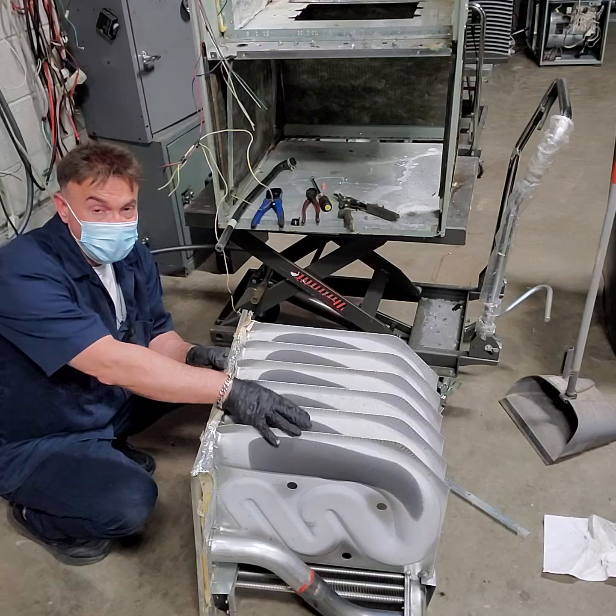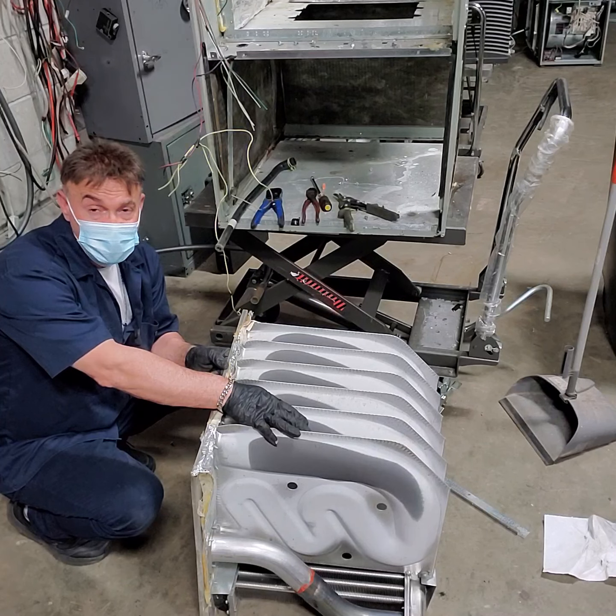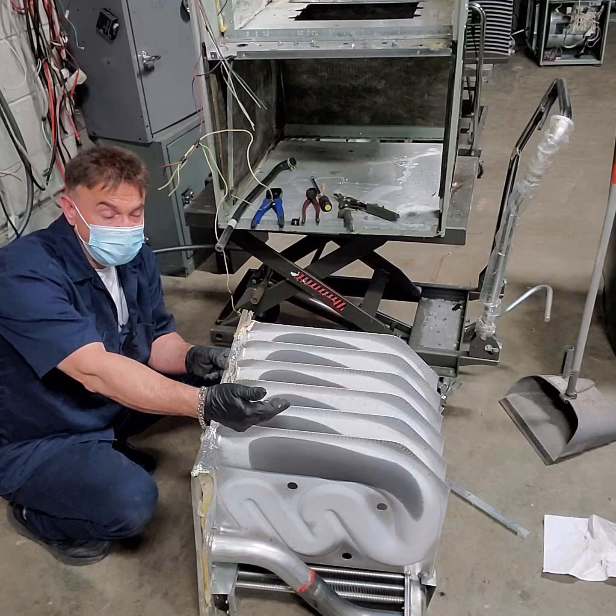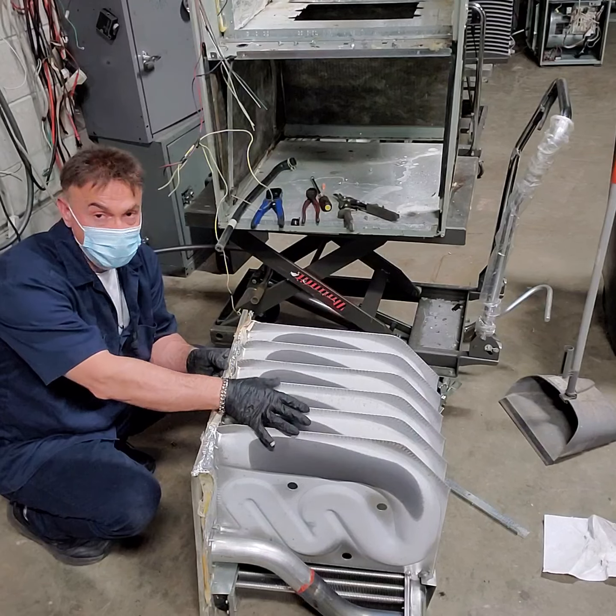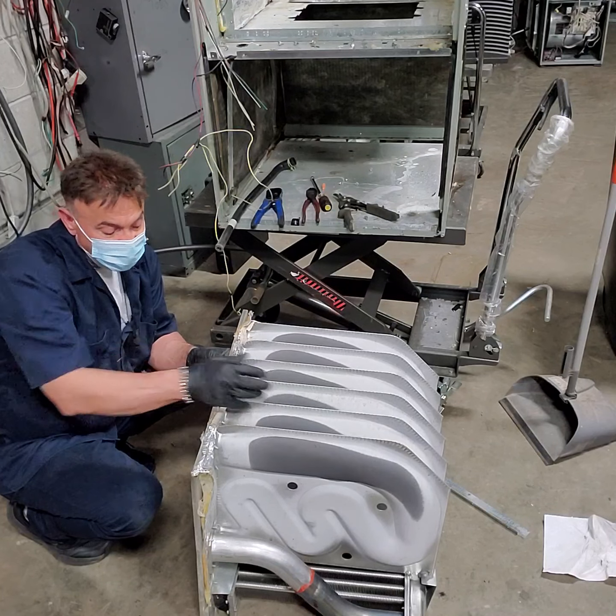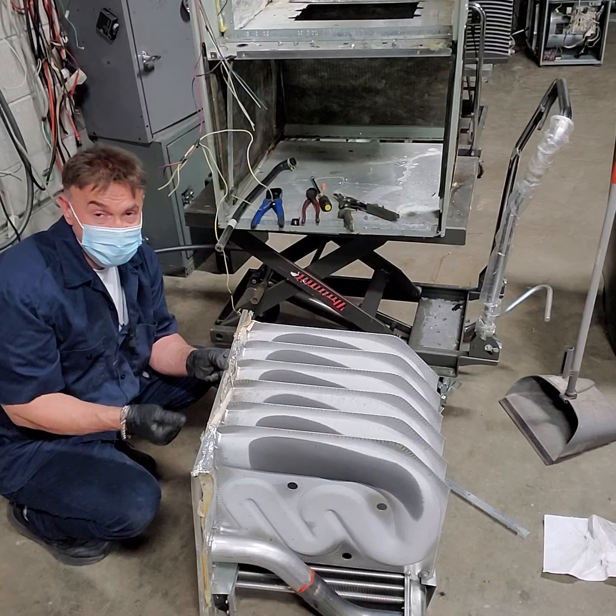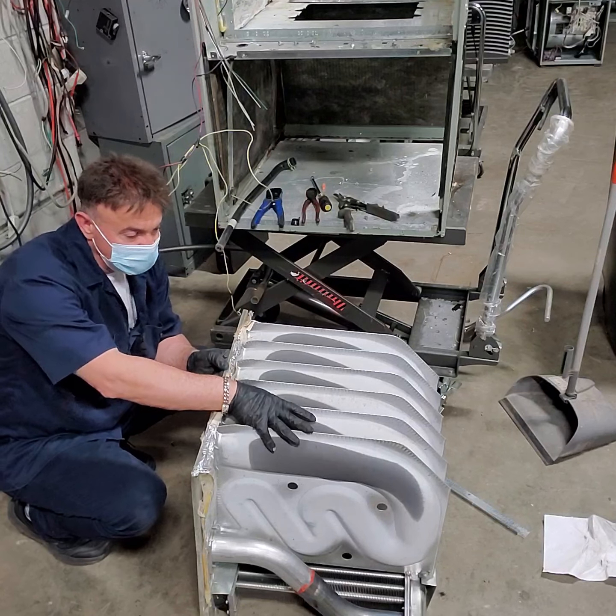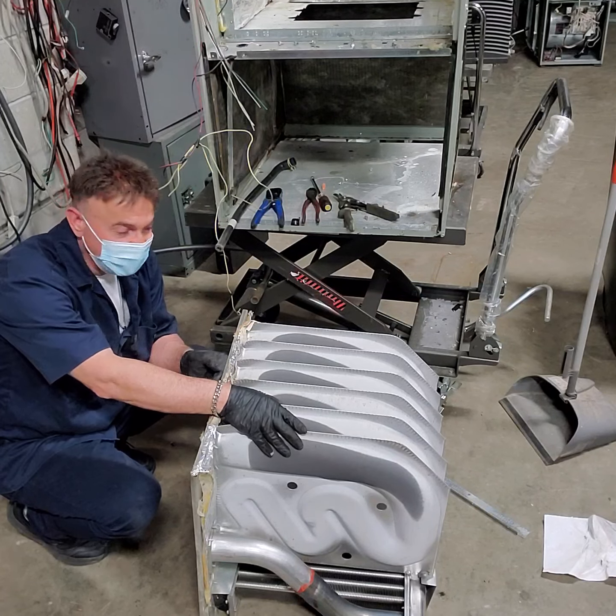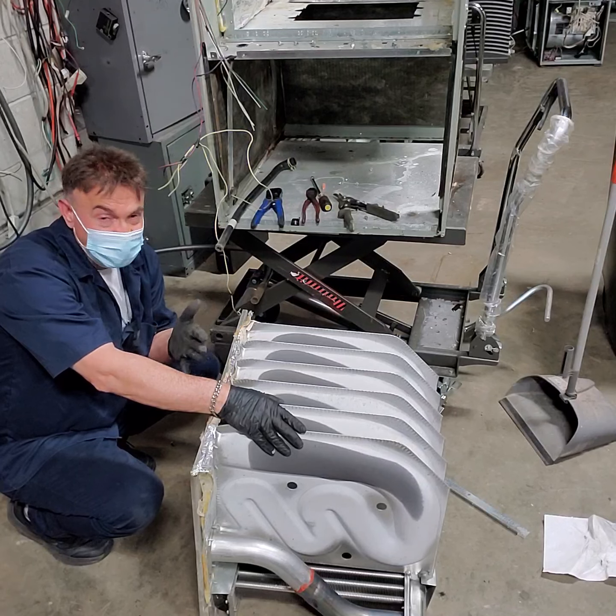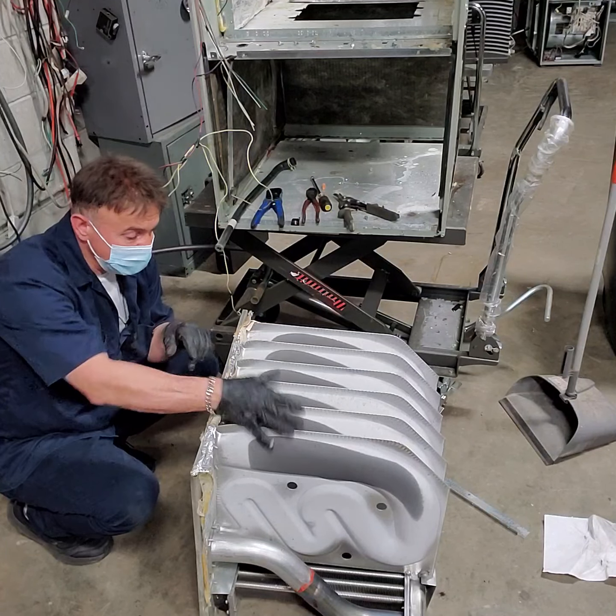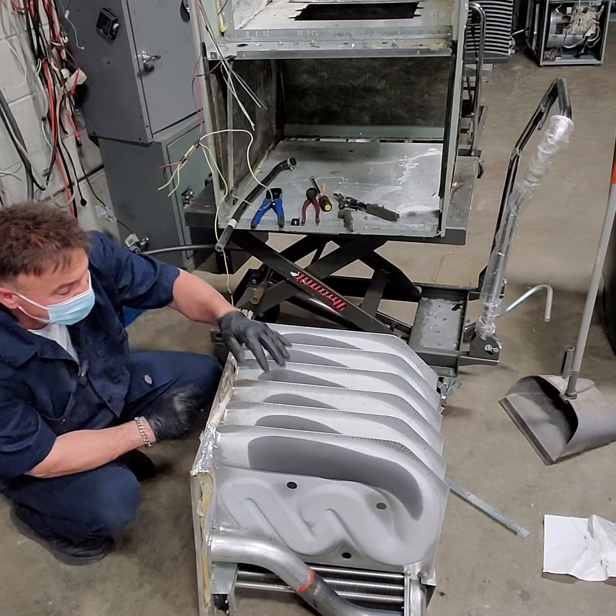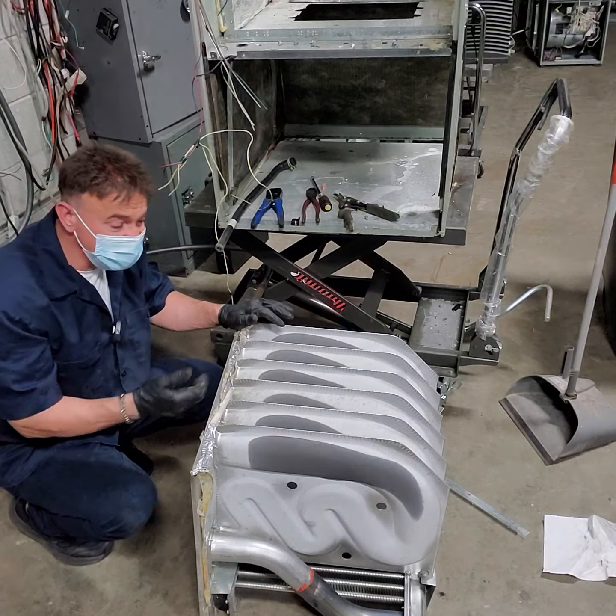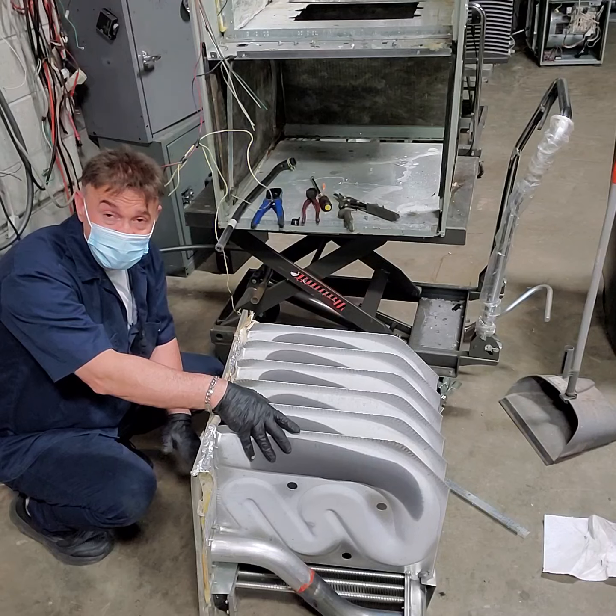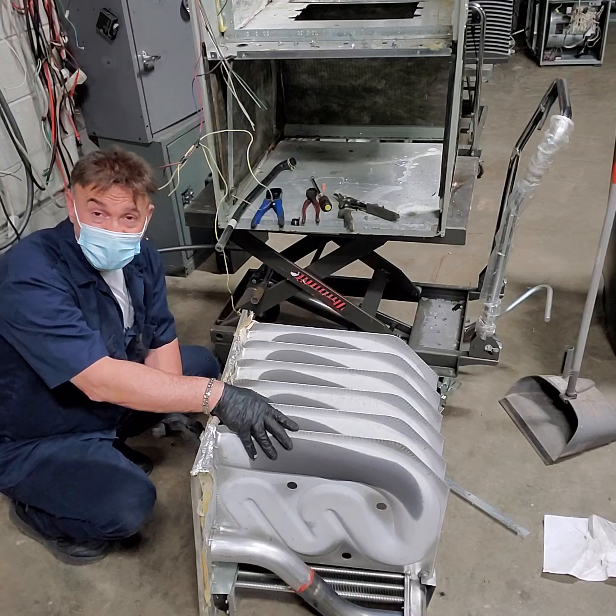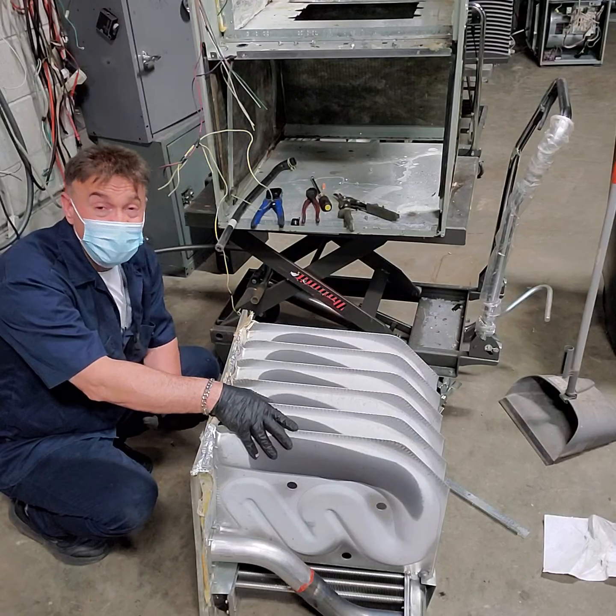Because if the house has good insulation, good windows, and the air coming out here is 105, 110, it will heat the house no matter what you do. But if the gas is open wide and you have like 180 degrees, it will heat the house as well. But nobody sees the real world. We see it. That's what happens to the heat exchanger. And if you have it adjusted, the furnace will work with less deterioration, less wear and tear, and will live forever.